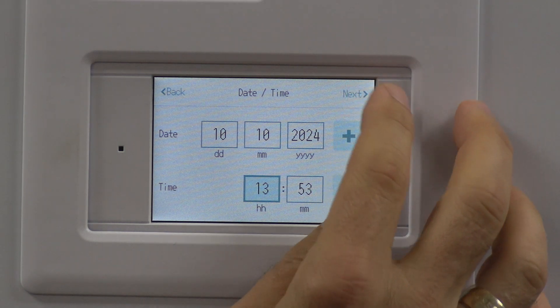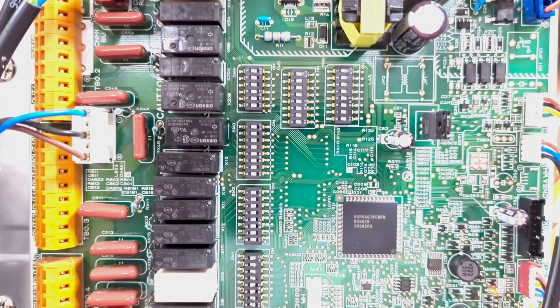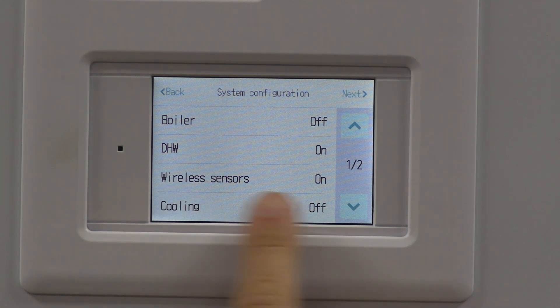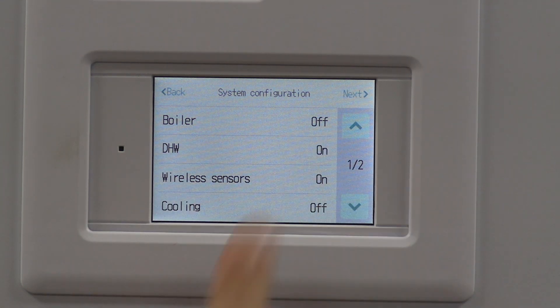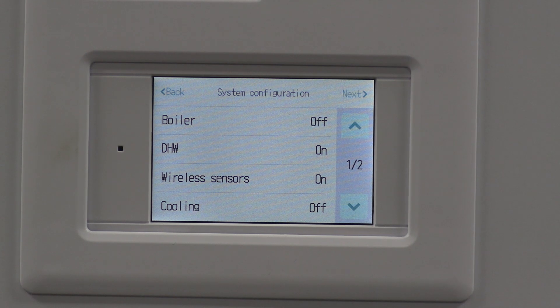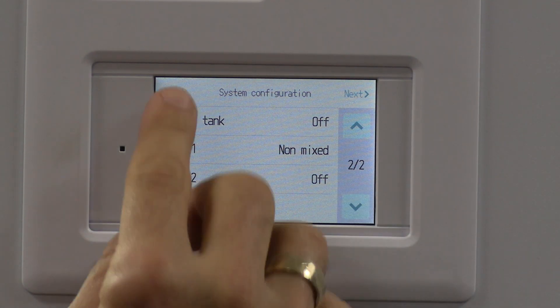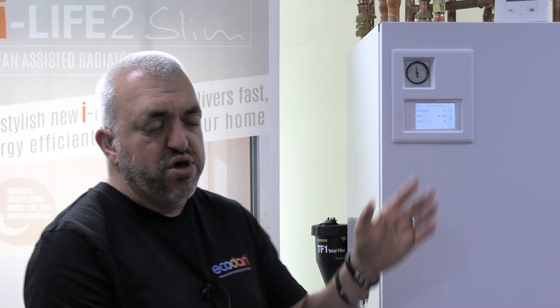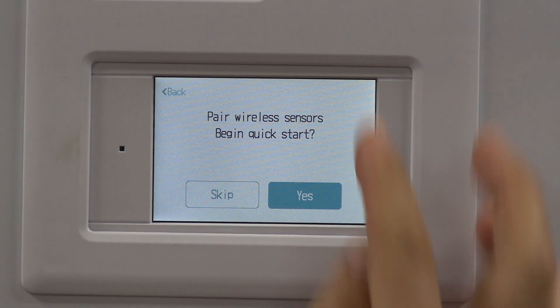The next one is a new function - it's going to ask about your setup. When you configure your DIP switches to tell the system what you're using, for example I'm using a Mitsubishi wireless room stat with two zones of heating, this screen lets you verify that your setup is correct. It shows boiler off, domestic hot water on, wireless room stat on - confirming the DIP switch is active. It's a quick and easy way to check your setup before you get too far into commissioning. It then prompts you: is this correct? As long as you're happy, move on.